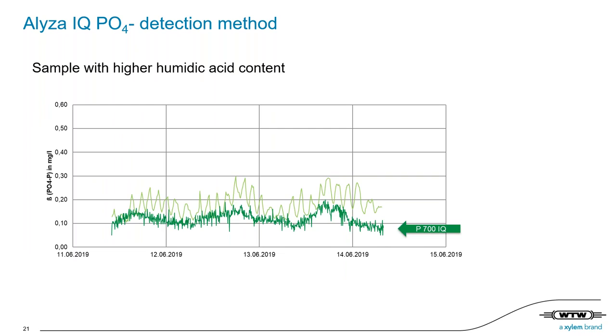Here is an example of the new yellow method using reagent A and B compared to the P700 IQ measurement. The sample has a high humic acid content, leading to a yellowish or brownish coloration itself. This leads to an overestimation of the blank measurement and thus too low measuring values, clearly shown, as you can see here for the P700 IQ. Alyza IQ with only reagent A leads also to the same underestimated results. But in contrast, Alyza IQ shown here using reagent A and reagent B displays the correct measurement results. So this is a clear advantage, especially for colored media or other difficult sample matrices with mixed wastewater, for example. So again, you always have the choice. Dependent on your application, we can give you the optimum performance.